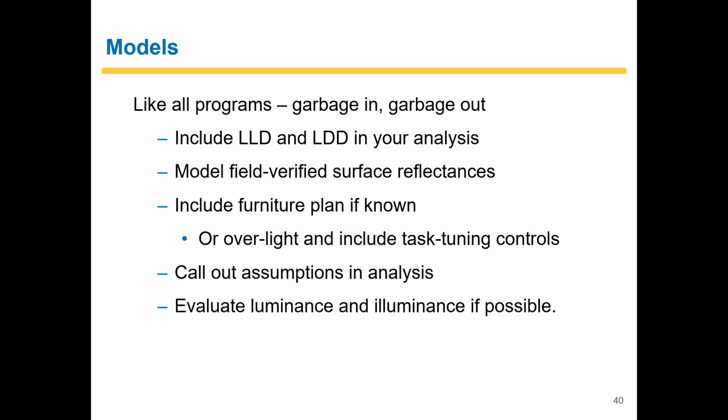Some guiding principles for any lighting model: you want to make sure that you're not putting garbage in, because you'll get garbage out. So make sure you're including lamp lumen depreciation and luminaire dirt depreciation in your analysis. Field verify the surface reflectances. Include the furniture plan, because there's a lot of blocking that happens with furniture. Make sure all those assumptions are called out in your analysis. And you might consider evaluating luminance as well as illuminance. Luminance is going to help you identify potential glare problems.